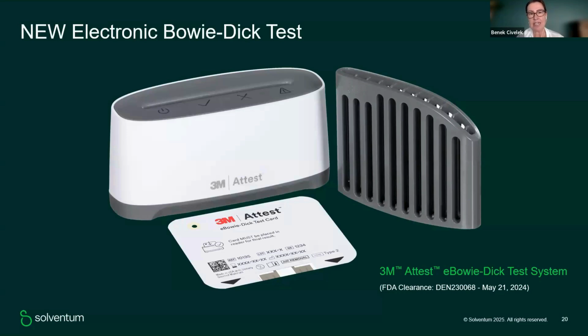When we're talking about Bowie-Dick, we're talking about numbers, hundreds of lots being tested under several conditions stated in the standard. There is a pass value, and there are fail values due to leak conditions or air injection conditions. This test fulfills all these requirements. It is composed of three items. The main part is the Bowie-Dick test card. The second, which you see on the right hand, is the card holder, which makes the test card easier to place inside the sterilizer. And we have the reader. If you are using fast-response biological indicators, you have to use the same type of incubator. Now this is designed for this test card.